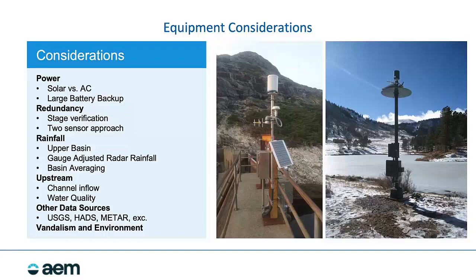Even if there's AC power, we see breakers trip a lot on some remote dams where the power is not reliable. So even with that AC power source, we want to make sure that we have the battery backup if there were to be a failure.